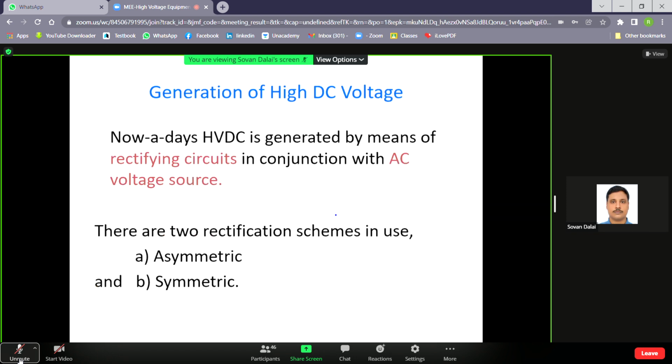Okay, before going to the detailed discussion of generation of high DC voltage, we can generate high DC voltage with the help of an AC voltage source, and according to the rectification scheme, these circuits are called asymmetric circuit and symmetric circuit. Okay, and just for your understanding, if the diodes conduct identically in both halves of the AC cycle, then this circuit is called the symmetric circuit. If the conduction periods of the diode are not identical in both halves, then this circuit is called the asymmetric circuit.